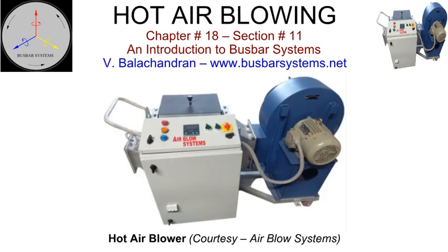designated discharge, a three-phase heater of adequate variable capacity, coordinated with the airflow rate to deliver air at the designated temperature, air ducts, manifolds, etc., as required, air filters at the inlet of the blower, airflow and temperature measurement at the discharge end of the blower, baffles and dampers to control and balance the airflow and the temperature in the field, control panel for distribution of power and control, metering and protection of blower and heater.